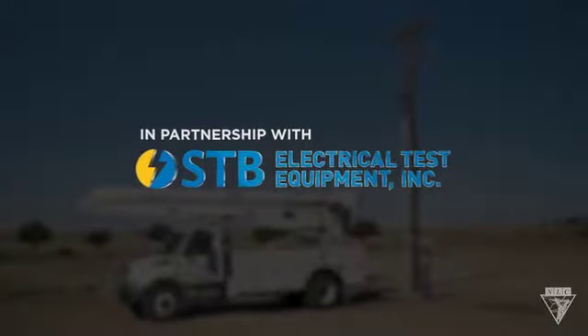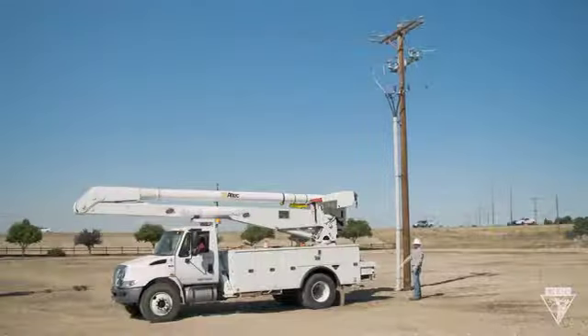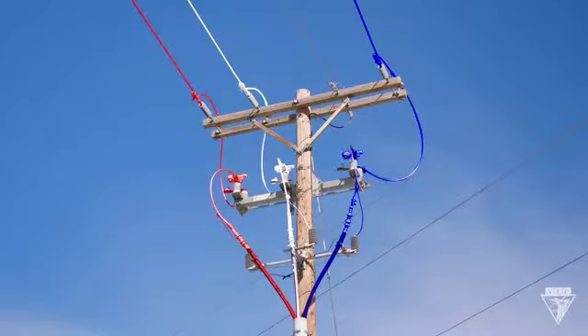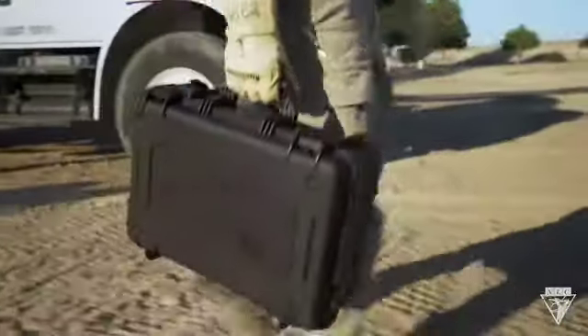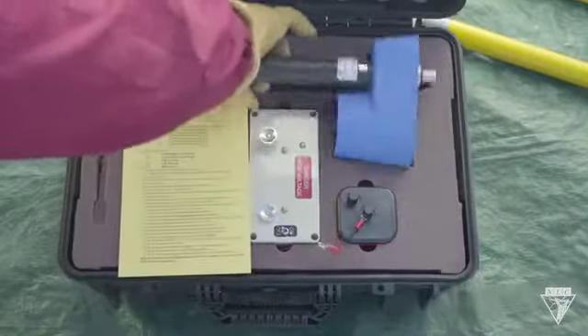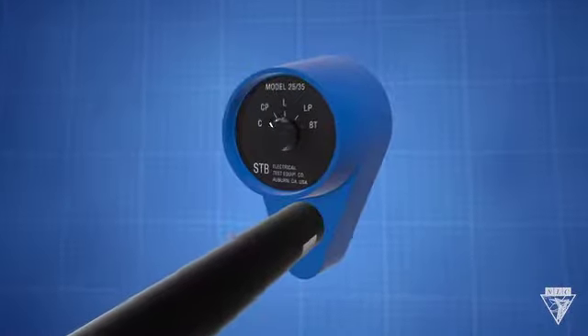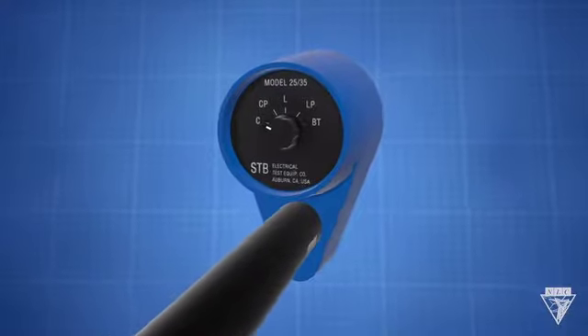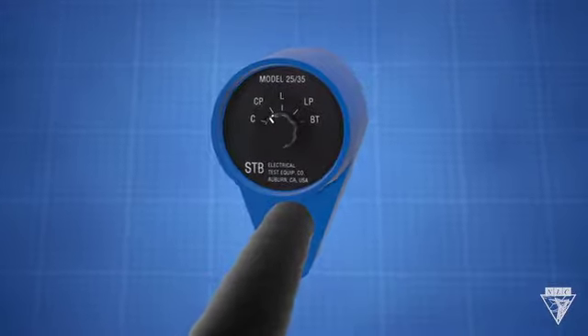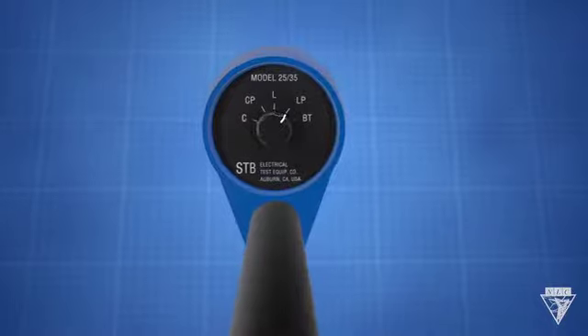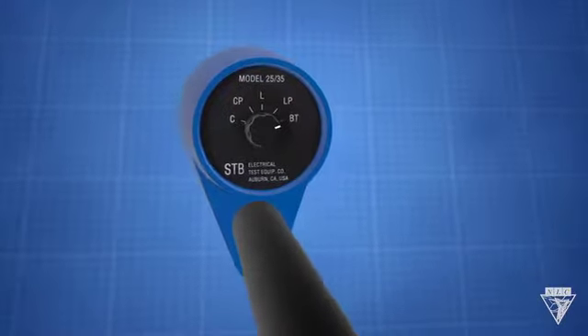Phasing out a circuit is the process of checking the voltage at an open point on a line to make sure the phases are in the right order. This should always be done before bringing two energized phases together. To check phase, we're going to use STB's phasing voltmeter. This meter has 5 different dial settings: capacitance tap sensing, capacitance tap phasing, line sensing, line phasing, and battery testing.